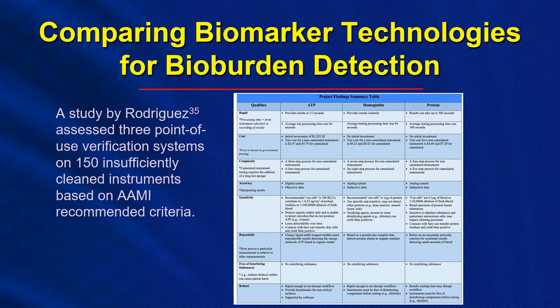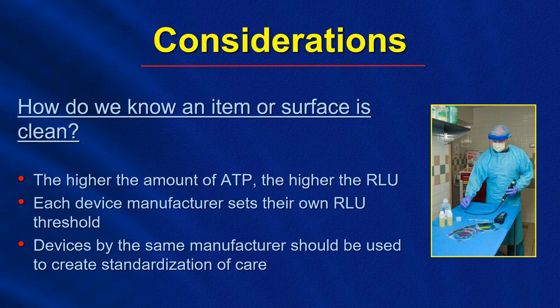So here are some considerations, and these next couple of slides may actually answer some of the questions that may come in later. A lot of people do ask, how do we know an item or surface is clean? Again, the higher the amount of ATP, the higher the RLU, the relative light unit. Each device manufacturer who manufactures ATP devices sets their own RLU threshold. Devices by the same manufacturer should be used to create standardization of care. And ultimately, with ATP cleaning verification systems, the higher the amount of ATP measured, the higher the RLU value, and any number over that set value would indicate a poor job of cleaning or cleanliness.